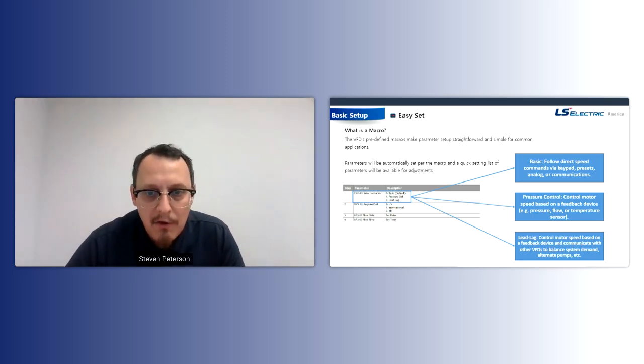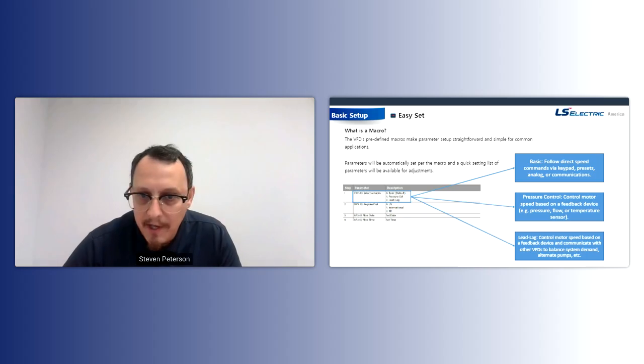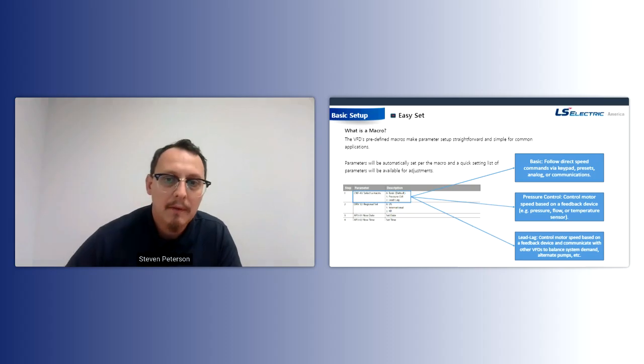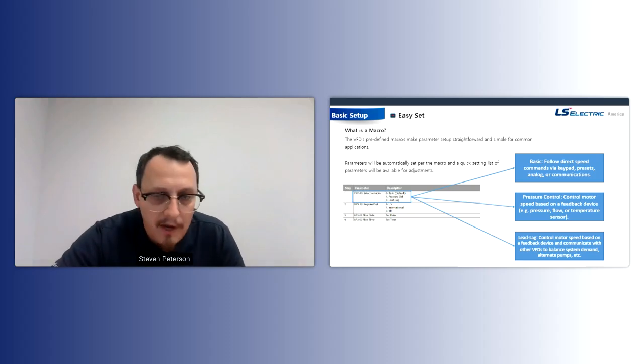And the last macro, lead lag setup. So that's PID control, but it's multiple drives and multiple motors that are connected together. And in our case, we use Modbus to connect the devices together, the VFDs. And what it's going to do, once you set up all the drives for lead lag control in the macro, is try to balance the system demand and alternate pumps, all based on what you program into the VFD.